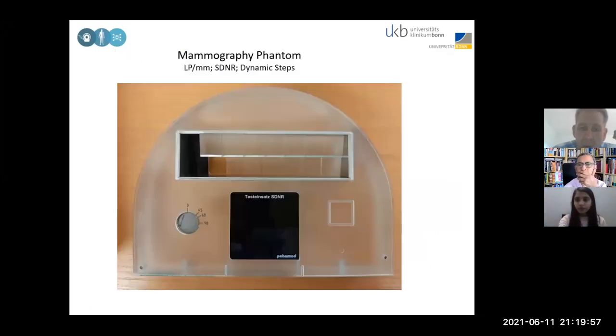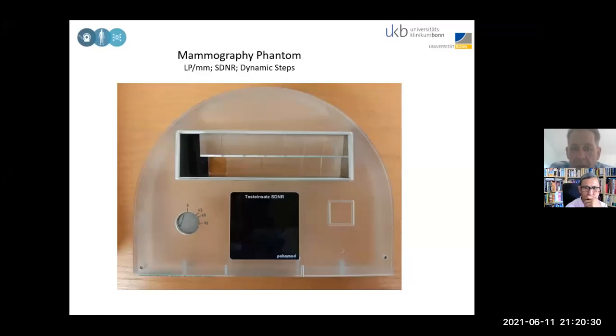So how this is tested: this is one of those mammography phantoms. You see here in the lower corner the numbers 0, 45, 60, and 90 degrees. These are line pairs per millimeter. If you image that, then you see there are small lines, and you can see the line profiles. I will show you a device later on where you could see a little bit more in detail. Then you see an absorption step. In the upper part you can irradiate entirely through the phantom, and then the thickness of the PMMA starts to increase up to a fully absorbing step. That is the black block on the left-hand side. Then there is the black part in the middle. This is an SDNR, a signal-difference-to-noise ratio device, where you could calculate how good your signal is relative to the noise coming from the entire phantom.